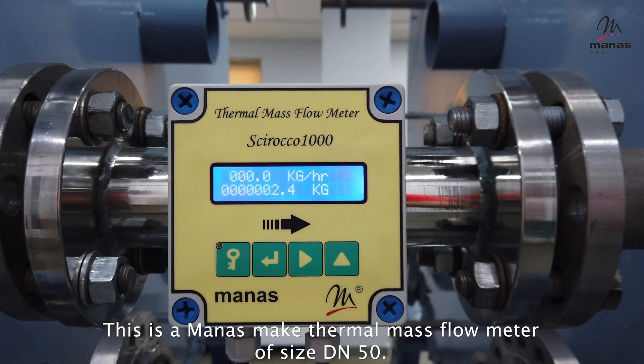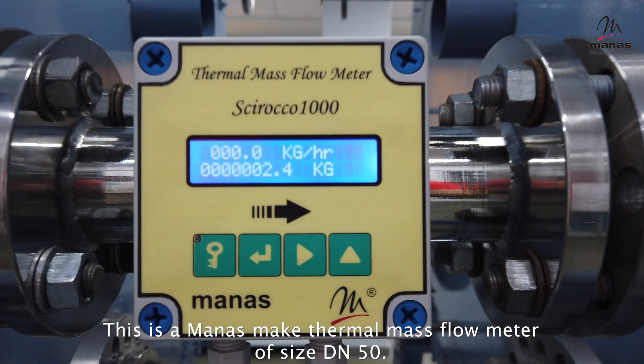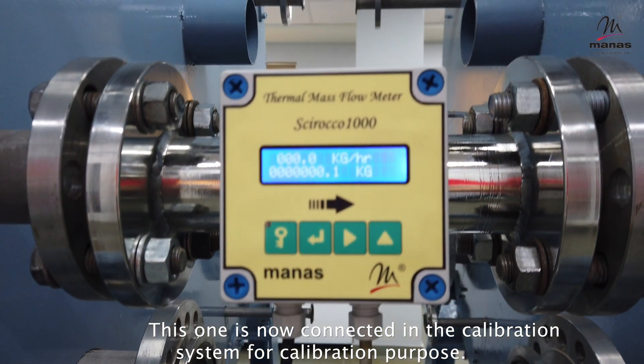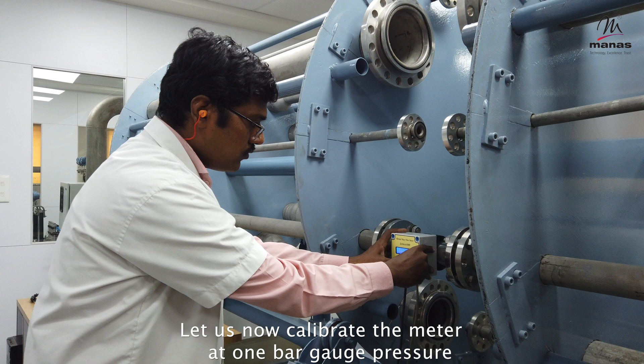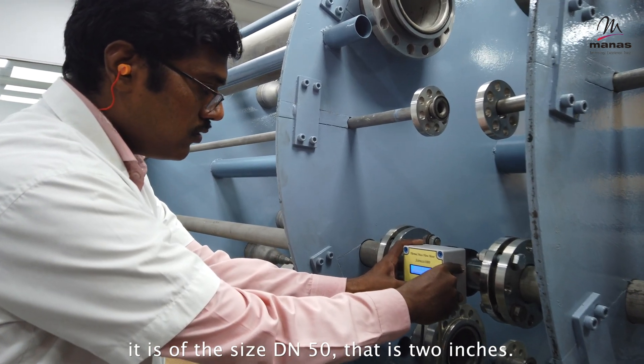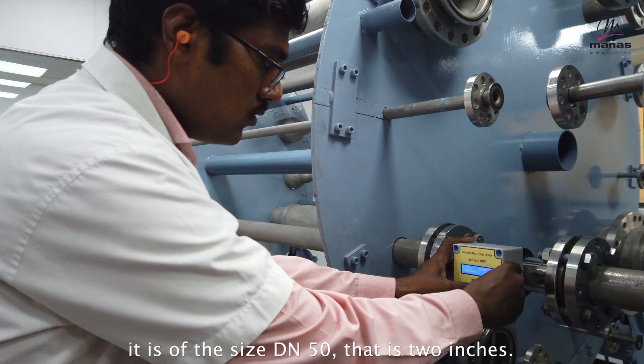Now we will see how an air flow meter is calibrated. This is a Manas make thermal mass flow meter of size DN50, that is 2 inches, now connected in the calibration system for calibration purpose. Let us calibrate the meter at 1 bar gauge pressure.